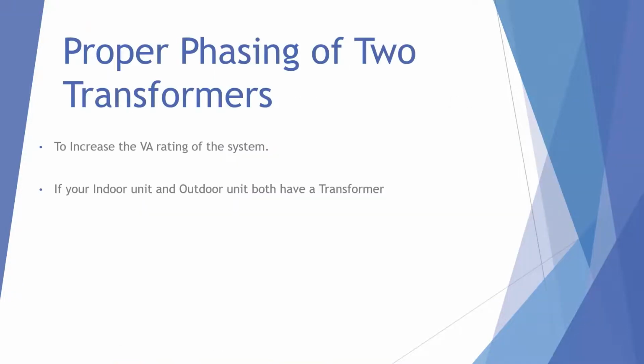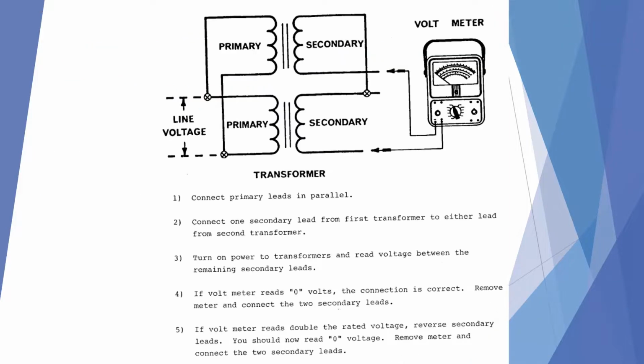Another thing that you want to be aware of when having 2 transformers in a system is they need to be properly phased so they don't blow the fuse or blow one of the transformers. The reason for having 2 transformers sometimes is to increase the VA rating of the system, or in some particular applications, you may have a transformer in the indoor unit and in the outdoor unit. In order to do this, you need to make sure that the transformers are properly phased together.